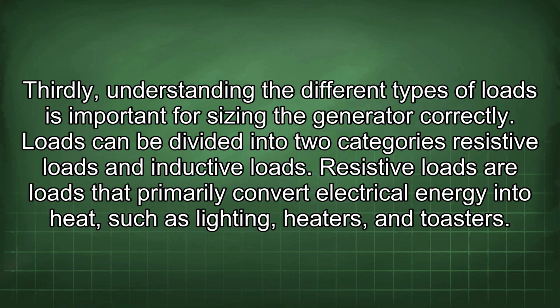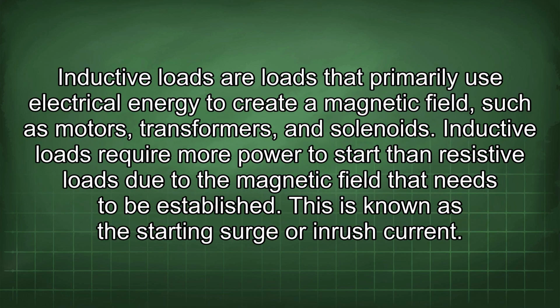Thirdly, understanding the different types of loads is important for sizing the generator correctly. Loads can be divided into two categories: resistive loads and inductive loads. Resistive loads are loads that primarily convert electrical energy into heat, such as lighting, heaters, and toasters. Inductive loads are loads that primarily use electrical energy to create a magnetic field, such as motors, transformers, and solenoids. Inductive loads require more power to start than resistive loads due to the magnetic field that needs to be established. This is known as the starting surge or inrush current.